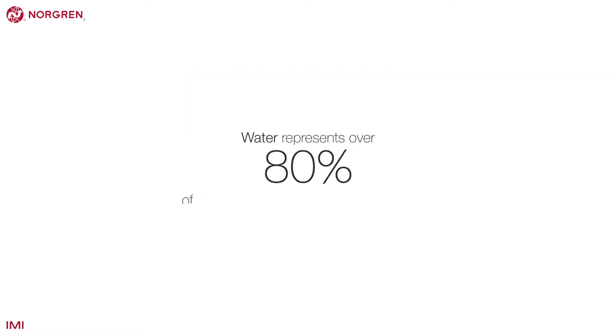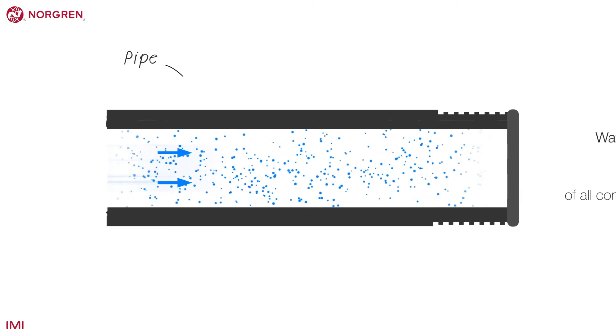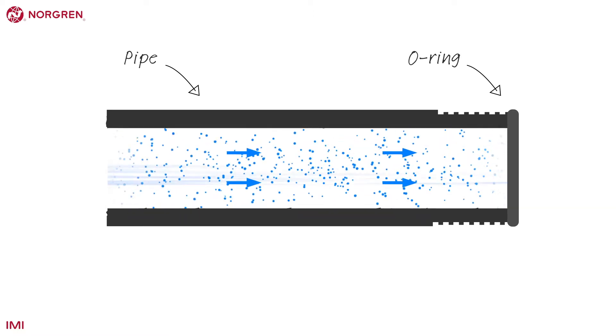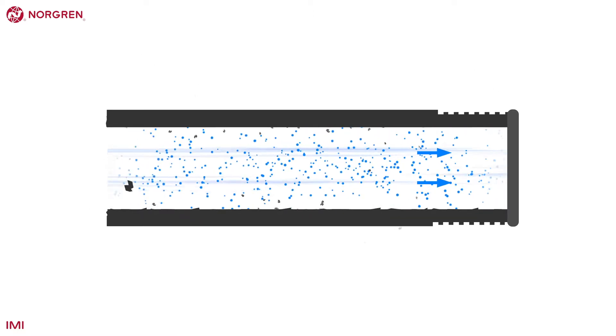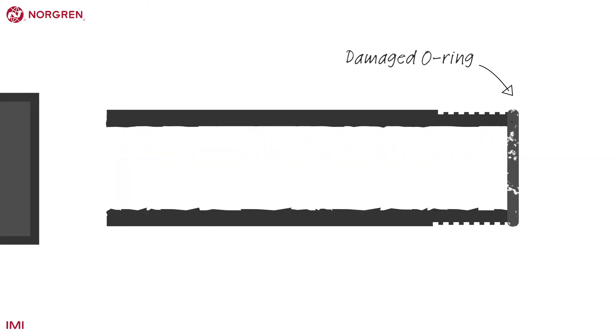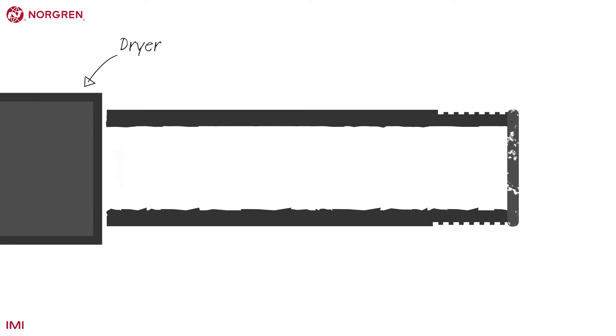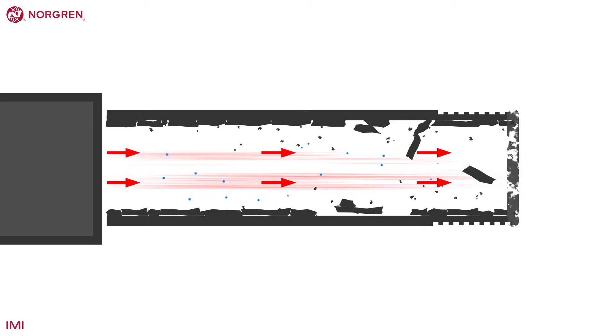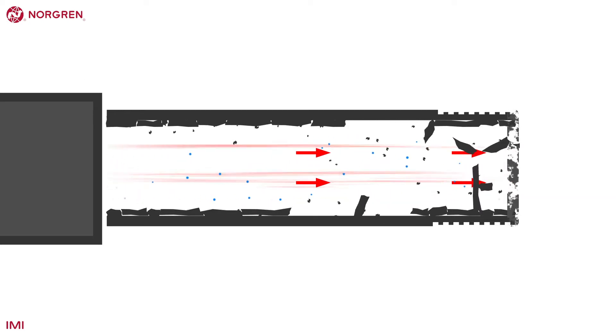Water represents over 80% of all contamination within compressed air. Wet air causes corrosion through the entire system and reduces the lifespan of components. Fragments of corroded piping can end up being fired through the system and cause significant damage. Adding a dryer to an existing system that is already suffering from corrosion can actually exacerbate this problem, causing more fragments to become loose in the system.